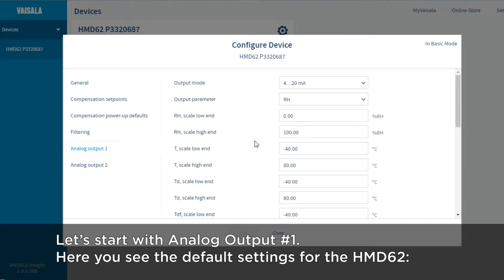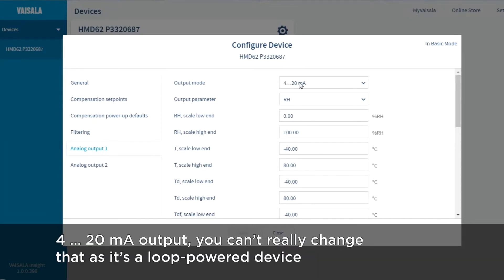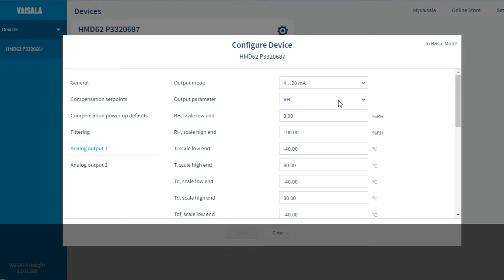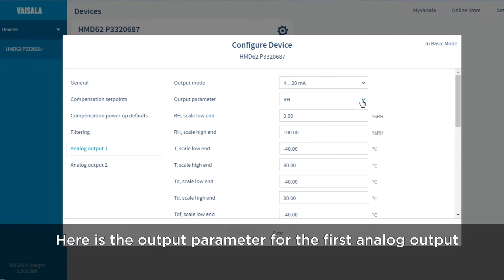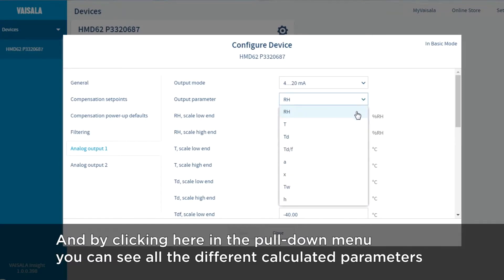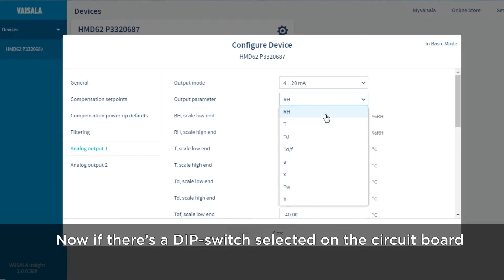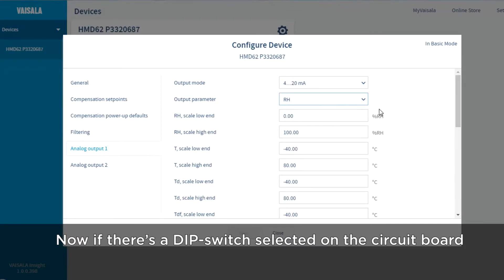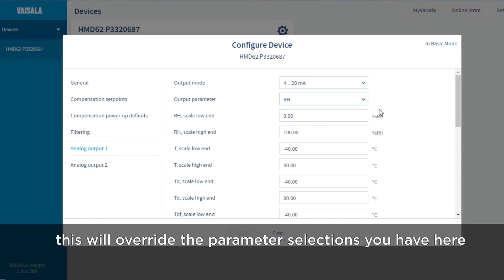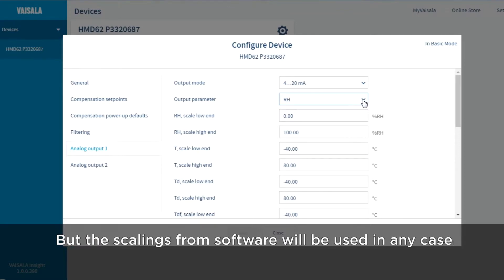Here you see the default settings for an HMD-62 device. It's a 4 to 20 milliamp output and you can't really change that — it's a low-powered device. But here is the output parameter for the first analog output, and by clicking on the pull-down menu you can see all the different calculated parameters. Note that if there is a dip switch selected on the circuit board, this will override the parameter selections you have here, but the scalings from the software will be used in any case.